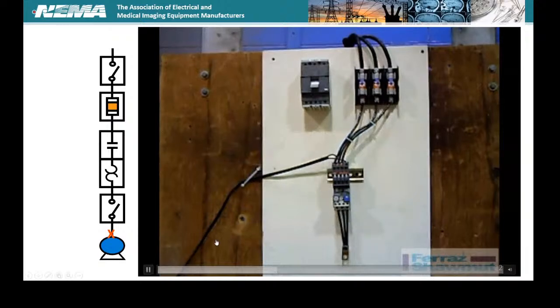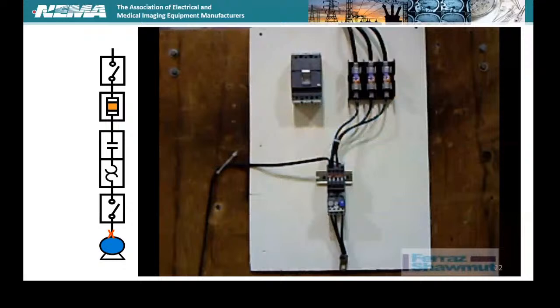And what this definition is all about is type 1 protection coordination on these blocks means it might be damaged and you may have to replace it, but there will be no hazard to equipment or personnel in doing it. Now, in that case, certainly you had a hazard, and that was a breaker that didn't provide type 1 protection. So what we're going to do is we're going to go through type 2 protection, and these are IEC rated contactors with the overload built into them. The fuses are going to go.